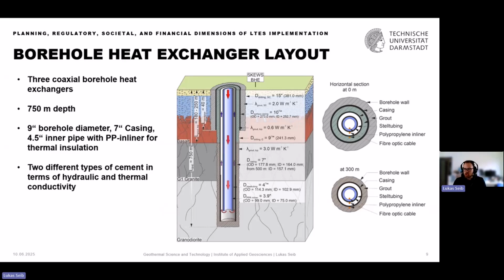This is the borehole heat exchanger layout we decided to go for. So we have a coaxial heat exchanger with, as I said, 750 meters of depth. We basically use standard API steel casing for the outer and the inner pipe. So we have an outer pipe out of steel to 750 meters, an inner pipe also to not completely 750 meters, but 745. And inside of this steel pipe, it's kind of special, is this blue pipe, a polypropylene inliner. So this basically is to reduce the thermal short circuit between the inner pipe and the outer pipe. We also have this plastic pipe in there.